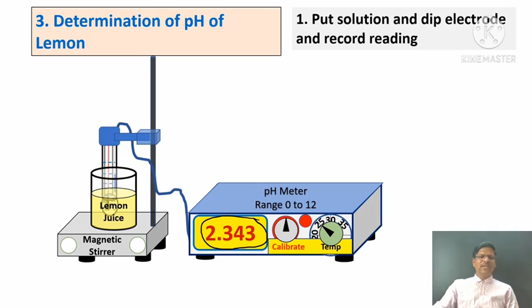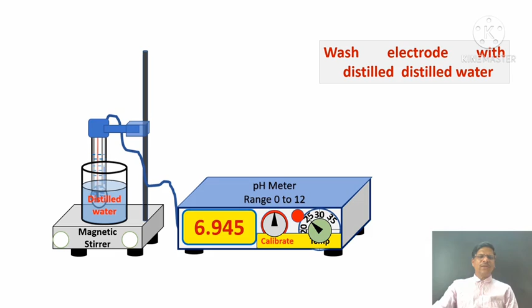What it means is that all the apple juice is washed out from the glass surface. Next step, lemon juice. Dip the combined glass electrode into it and wait till the pH becomes constant. Okay. So for the lemon juice, the pH is 2.343. So you have to note down this reading. Again, the next step is to wash with distilled water. Washing the glass electrode every time is necessary to avoid contamination and errors in the pH determination. Okay, so after the washing process, the pH of water is 6.945.